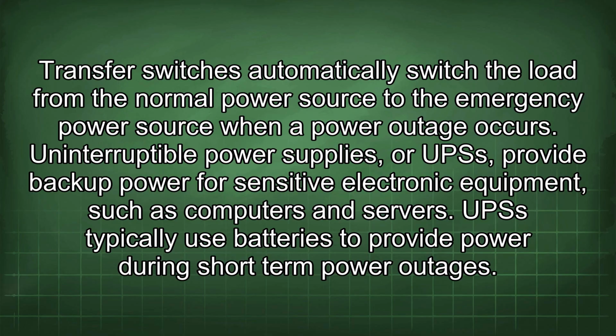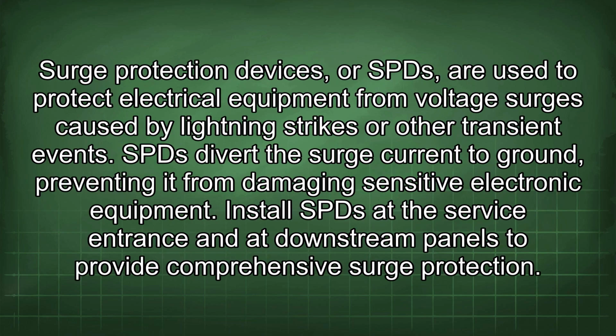UPSs typically use batteries to provide power during short-term power outages. Surge protection devices, or SPDs, are used to protect electrical equipment from voltage surges caused by lightning strikes or other transient events. SPDs divert the surge current to ground, preventing it from damaging sensitive electronic equipment. Install SPDs at the service entrance and at downstream panels to provide comprehensive surge protection.